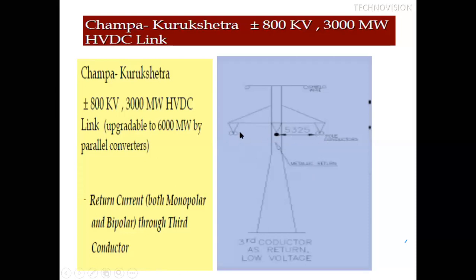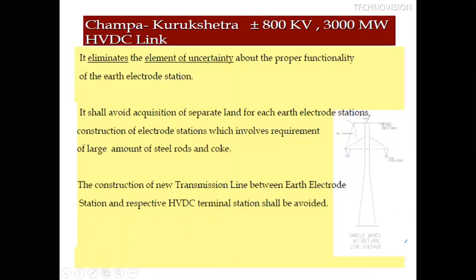Whenever it is in bipolar mode, this third conductor is used as a return path for whatever current difference there is between the 2 poles. That current flows through this middle conductor. So here there is no requirement of any electrode station. There are many disadvantages of electrode stations. So they have used this new technology in the Champa Kurukshetra ultra high voltage HVDC.